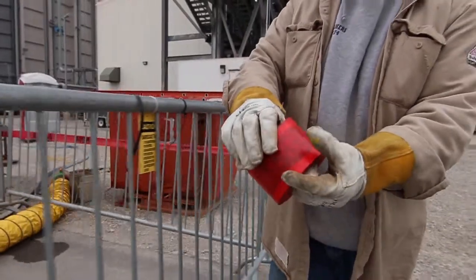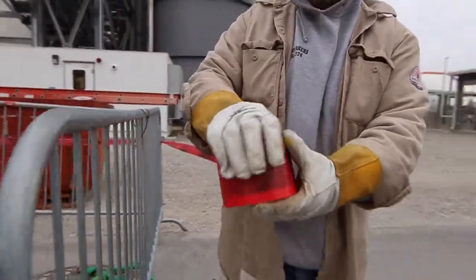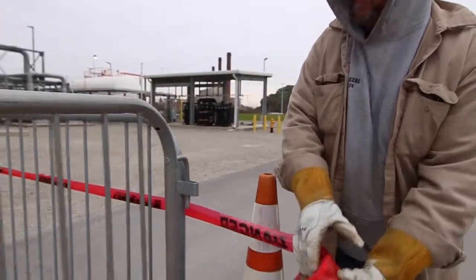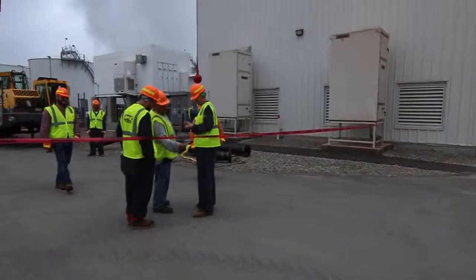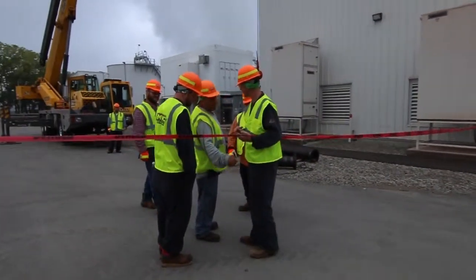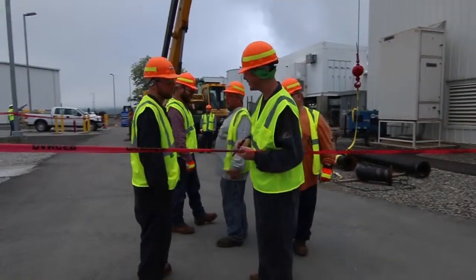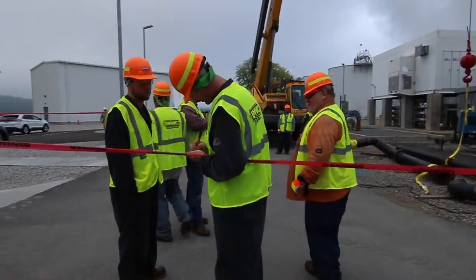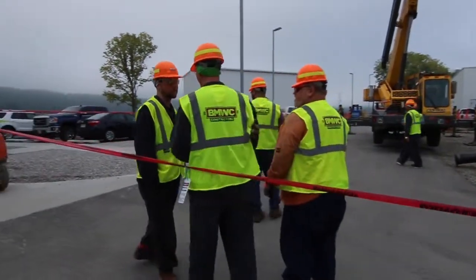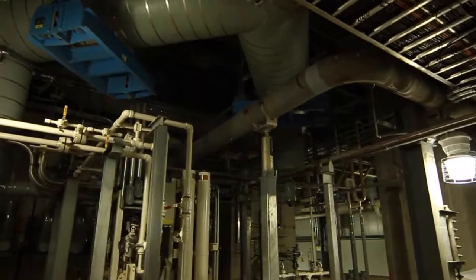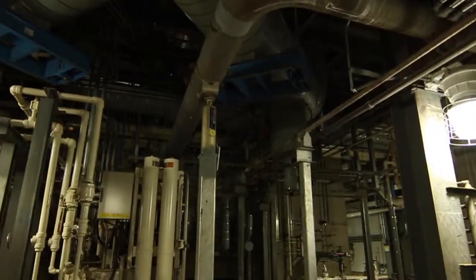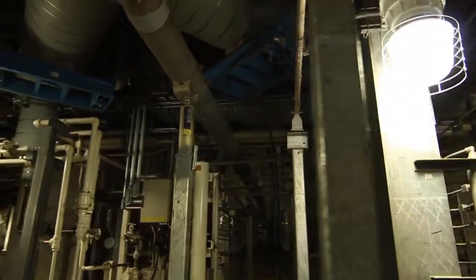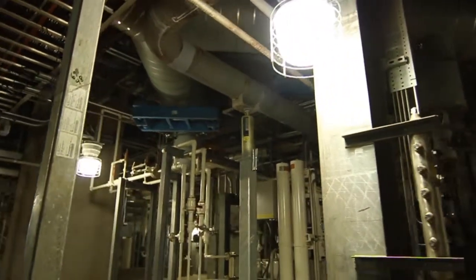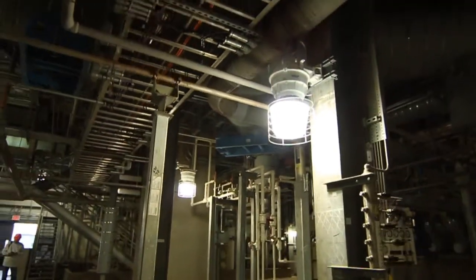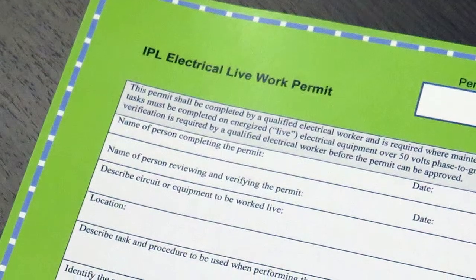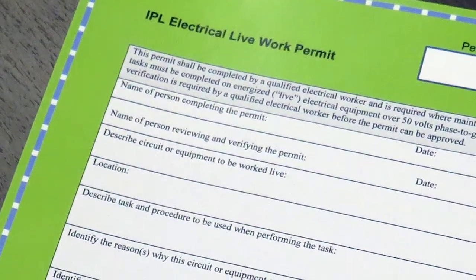If barricades and signs do not provide sufficient protection or cannot be used, an attendant must be assigned to warn and protect unqualified people. The primary duty of the attendant will be to keep non-qualified people out of the work area where electrical hazards exist. The attendant must remain in the area as long as there is a potential electrical hazard. When live parts cannot be placed into a de-energized state because the de-energizing produces greater hazards or it is infeasible due to equipment design or operational limitations, the task to be performed shall be considered energized electrical work and require the completion of an electrical live work permit before the work may begin.